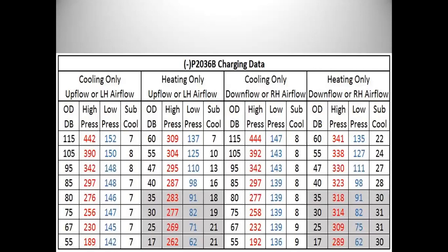Now, right here is a charging chart for a RP2036B. So it's very important here. This is on a 3-ton model. You'll see 2 sets of cooling, heating, cooling, heating. Now on the charging, on every chart, you'll see where it'll say UF/LH. So you have upflow and left horizontal airflow. Those are going to be in the same chart. If it's a downflow or a right flow horizontal, they're going to be in a different chart. If it's an air conditioning system, you'll usually see all coils or all orientations. It's just going to give you one chart to go by.